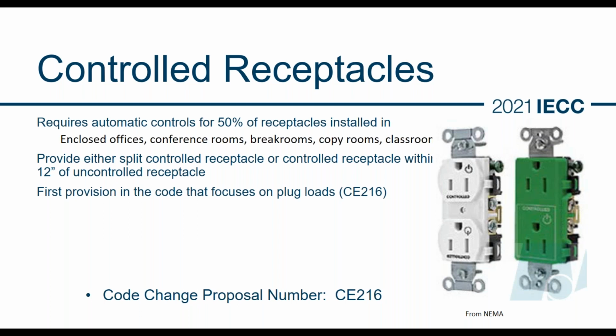So what we're trying to do right now is figure out how we can reduce the energy use for things that are plugged in, like desk lamps, computers, copy machines, things like that, that typically could be left on all night. So they drive a very high percentage of energy use in buildings. So this particular proposal will require that receptacles be switched automatically, so that if you're not there, they will turn off, and it requires 50% of the receptacles installed to be switched off.